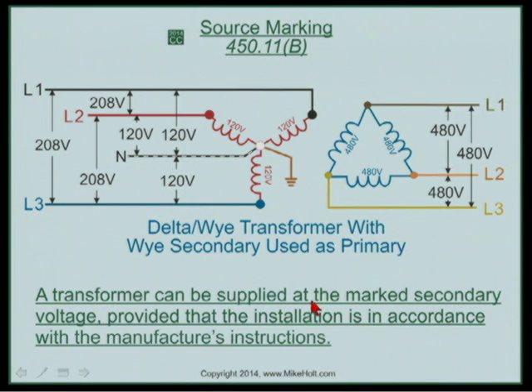Transformer can be supplied at the marked secondary voltage, provided the installation is in accordance with the manufacturer's instructions. This is done all of the time. And by the way, Mike, see this grounding right here? Get the grounding out of here. You don't ground the primary, and you don't bring a neutral to the primary when you backfeed a transformer.